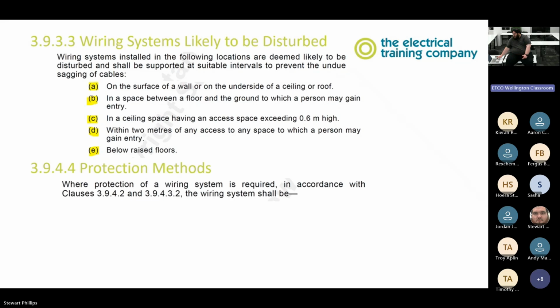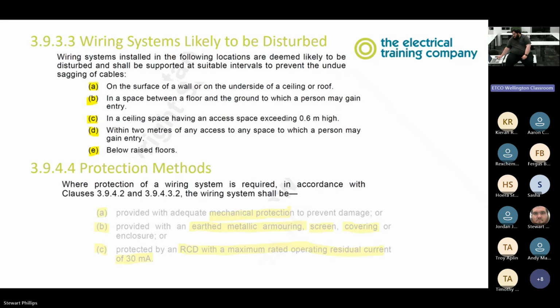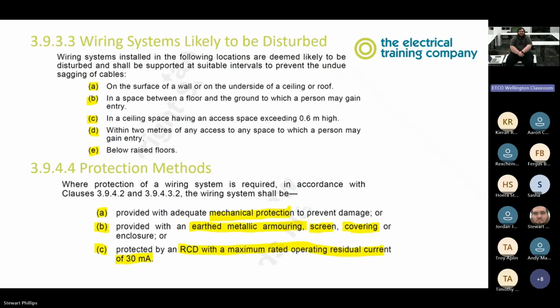So protection methods. Where protection of a system is required, the wiring system shall be provided with adequate mechanical protection to prevent damage, provided with an earth metallic armoring, screen, covering, or enclosure, or protected by an RCD with a maximum rated operational residual current of 30 milliamps. So an RCD for personal protection.